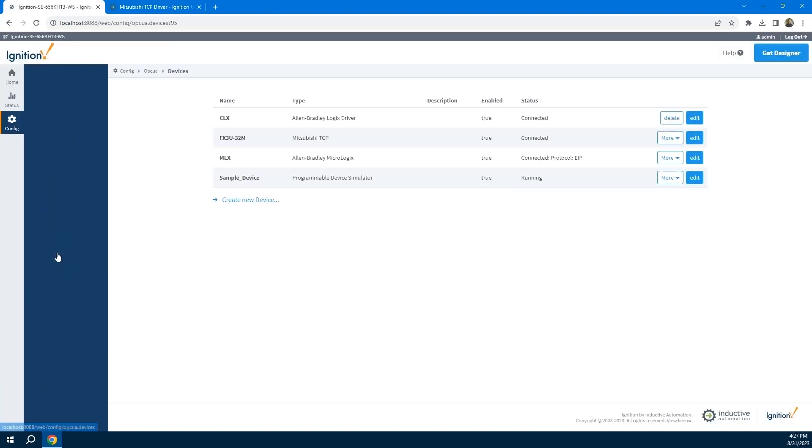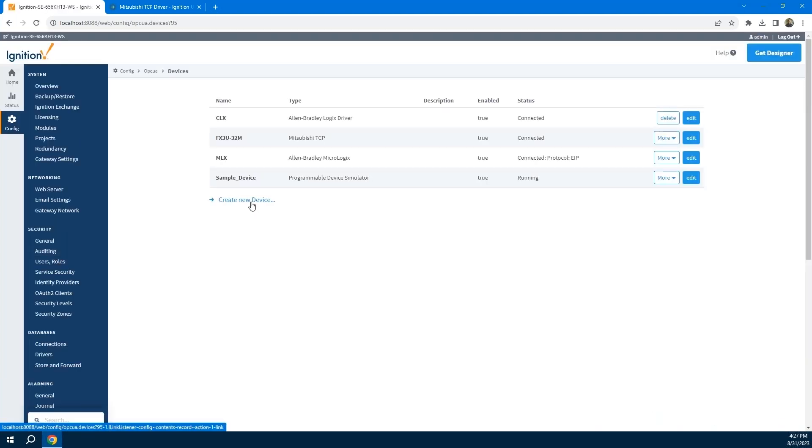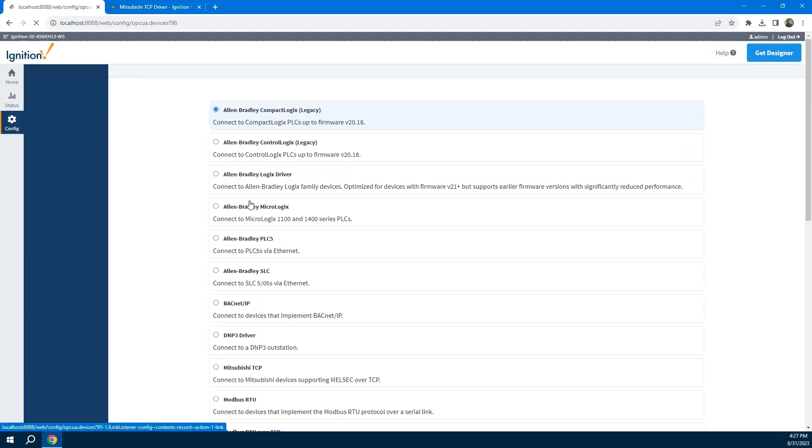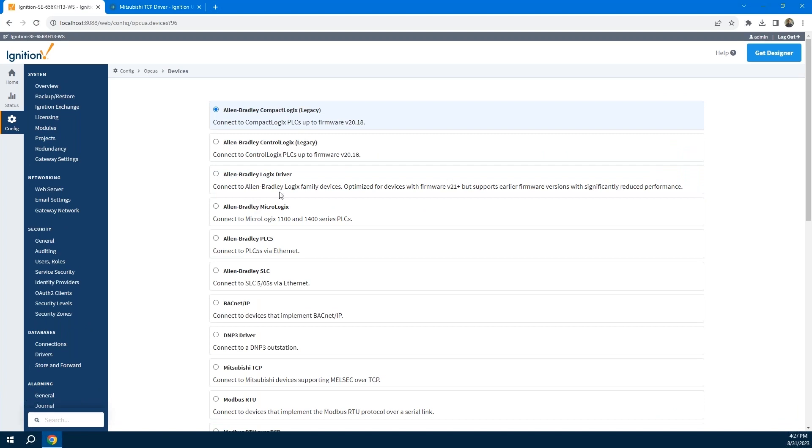If I go into that, I can see my devices and some devices like these Mitsubishi devices. When you first connect them, the protocol itself does not support browsing, so I can't actually see the tags that exist on my PLC. Other protocols do support that, where I can actually come in and see all of my configured tags. Once we connect to a device, we're going to talk about addressing and come back and show you what it looks like in this OPC quick client. When you don't have any tags, it looks like this - an empty tags folder. Now I'm going to come back here and create a new device.